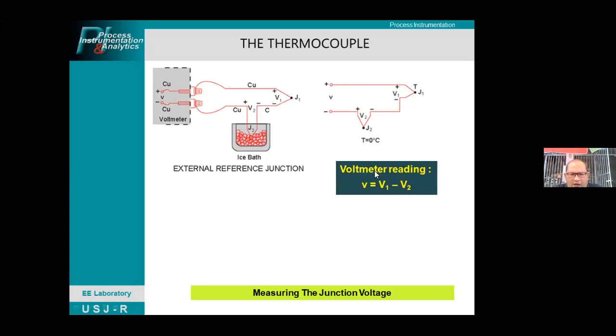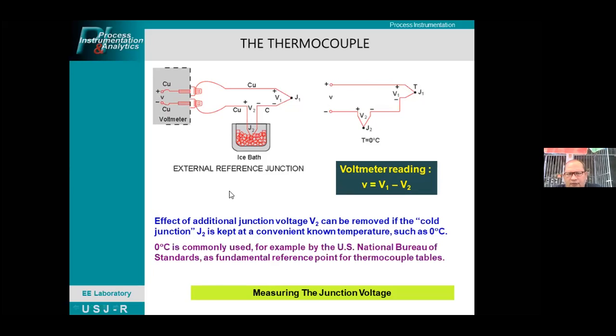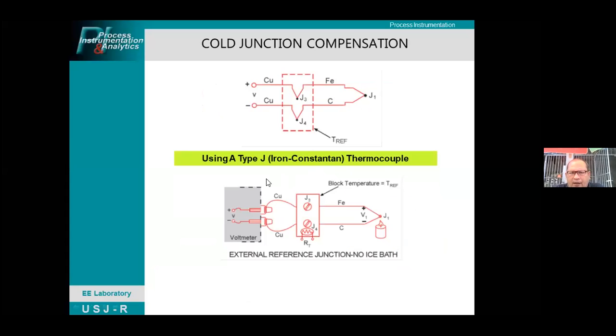The effect of the additional junction voltage V2 can be removed if the cold junction J2 is kept at a convenient known temperature, that is 0 degrees. The 0 degree centigrade is commonly used, for example, by the U.S. National Bureau of Standards as the fundamental reference point for the thermocouple tables. So we have tables for thermocouples to determine the particular reference junction. For copper and constantan, the type is type T. For the combination of iron and constantan, we call it a type J thermocouple.